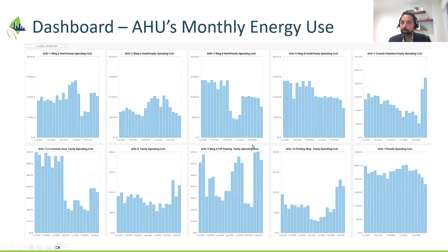Another dashboard is weekly reporting, which gives you a summary synopsis of the week: these are the faults in that particular week and these are the associated trends. A dedicated team looks into this, confirms what the issue is, and brings it back to the facility team to fix. In this case, there were some functional issues with the BAS, the command mismatching with the status, and fans underperforming. Some rules were triggered for this particular week.